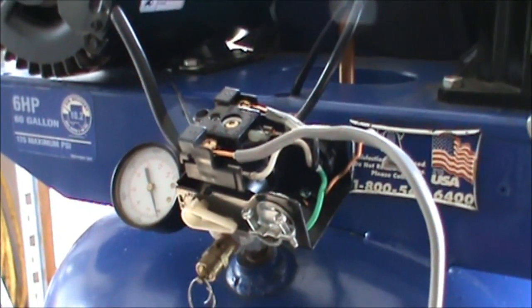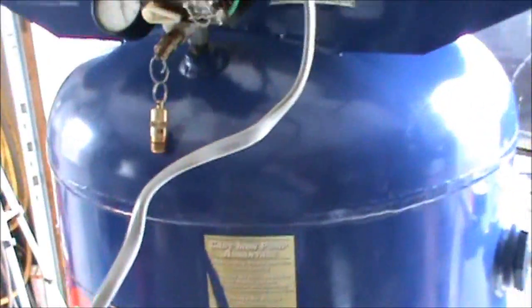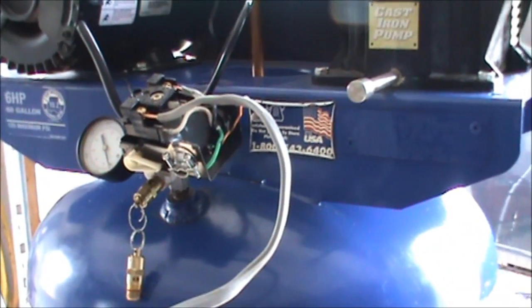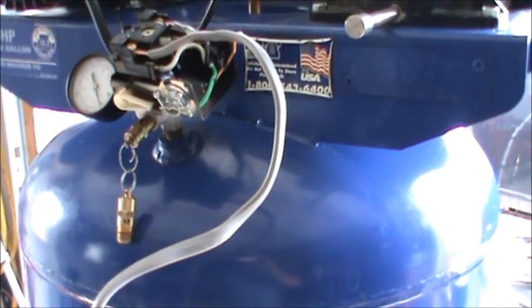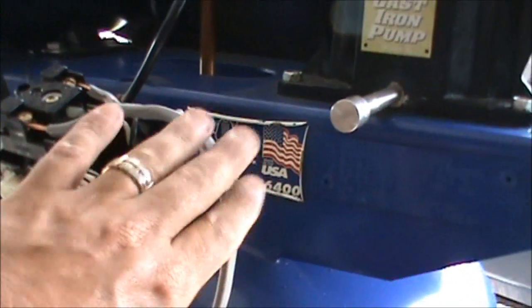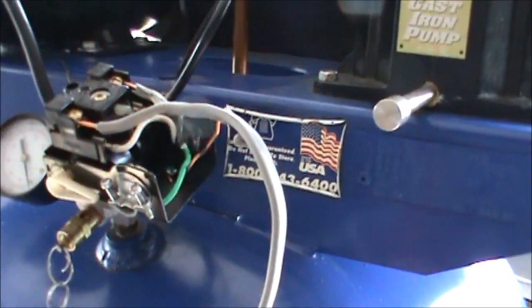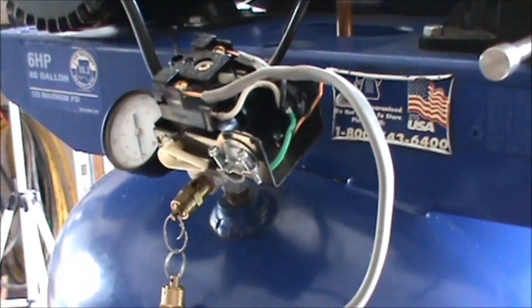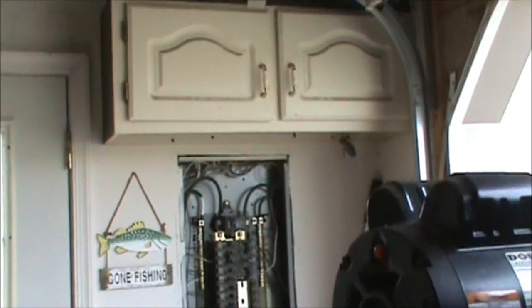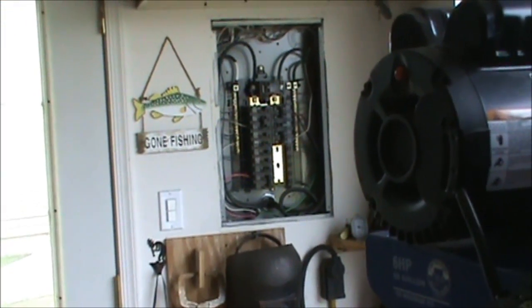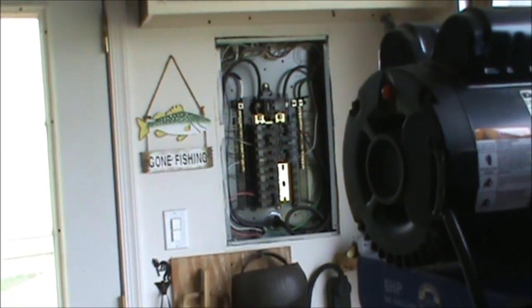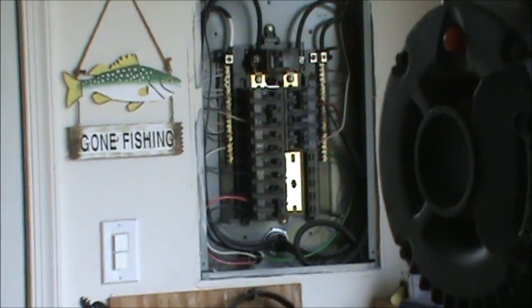The best way to run a circuit like this is to wire up your appliance first, whether it's an oven, an air compressor, or table saw. Have your wire run coming out the wall where you're going to hook up your appliance, take the wire, hook it up to the appliance first. That way the wire is dead, there's no electrons flowing through it, you can't get electrocuted. Hook that up first, then run your wire up through your walls, do your home run all the way back into the box, and then hook up your breaker. Once your breaker's hooked up, make sure your breaker's in the off position and you're going to insert it into the box.